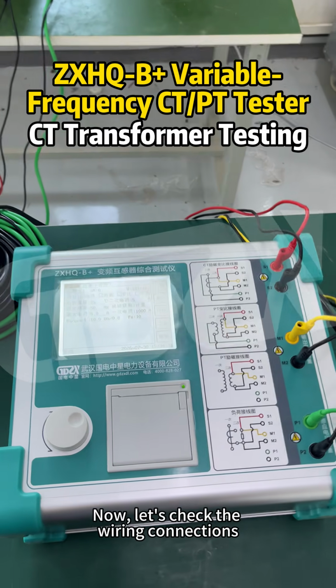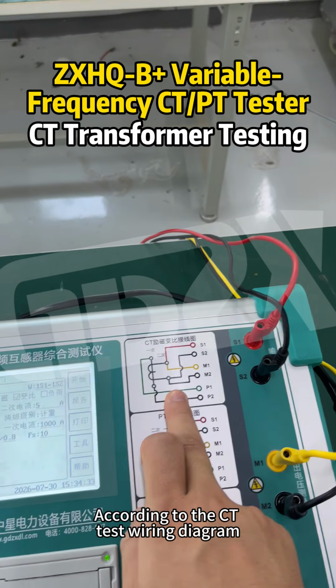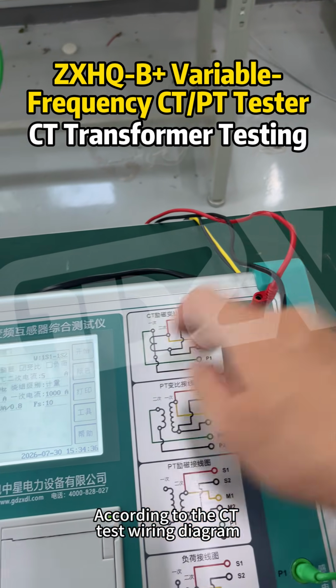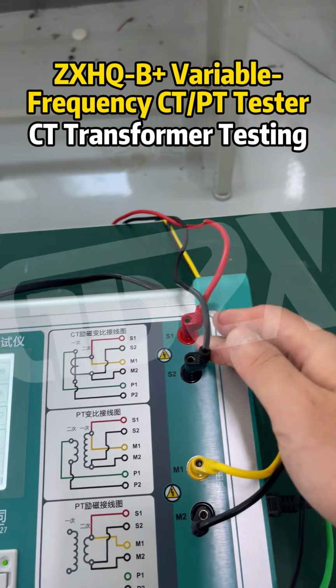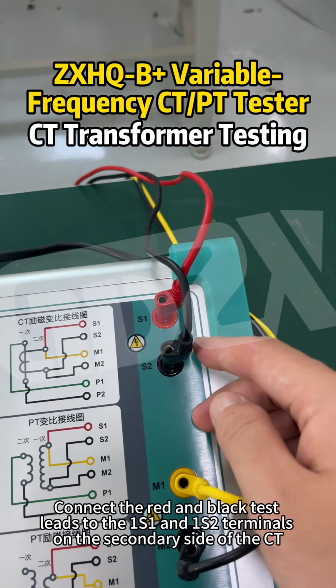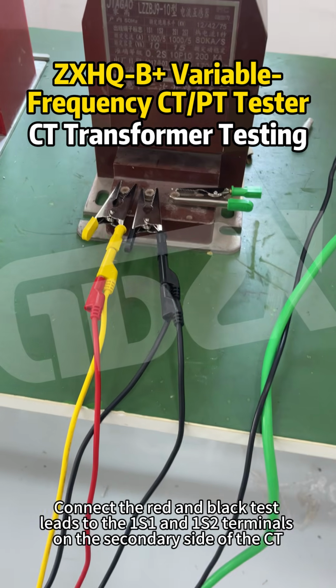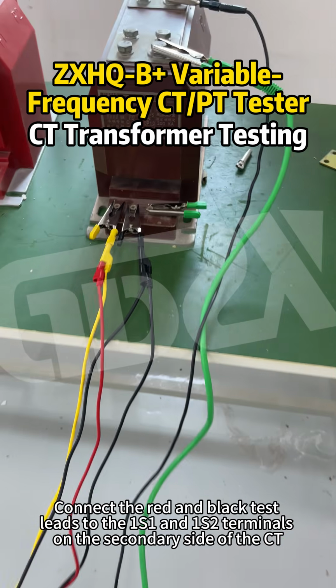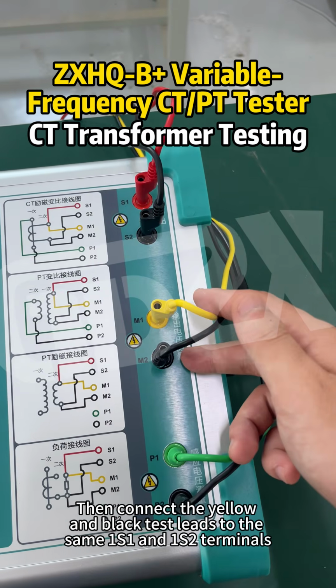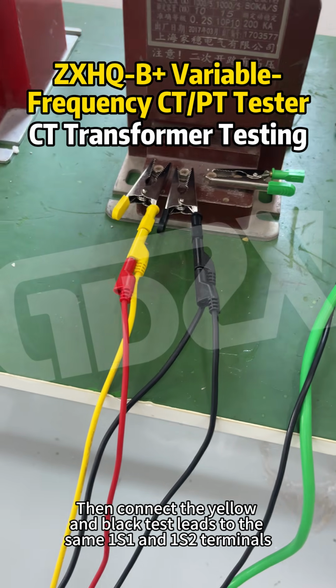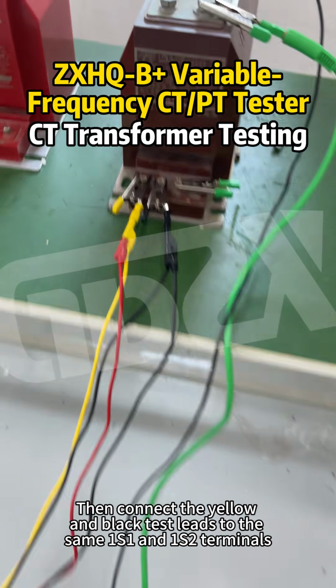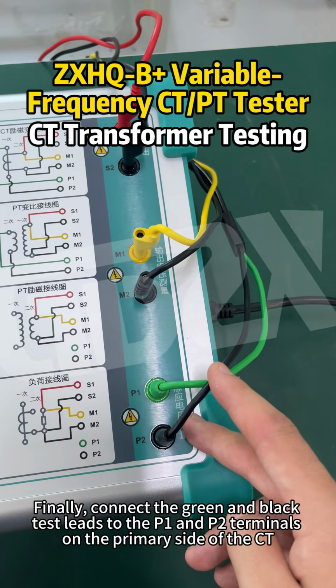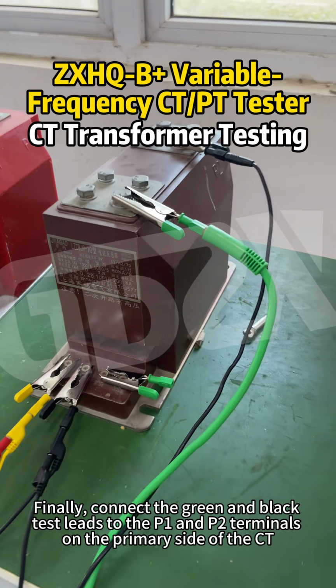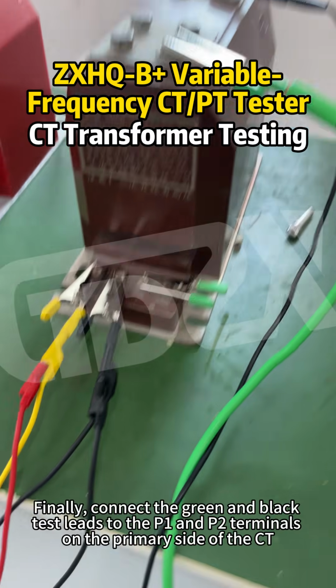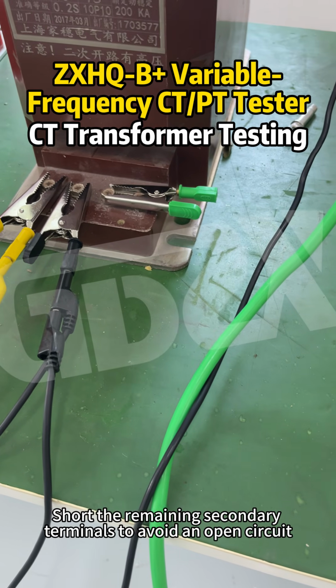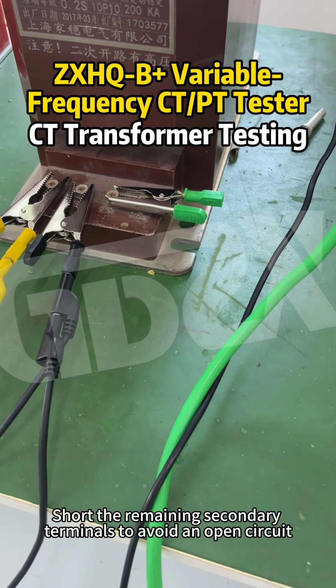Now, let's check the wiring connections. According to the CT test wiring diagram, connect the test leads as follows. Connect the red and black test leads to the 1S1 and 1S2 terminals on the secondary side of the CT. Then connect the yellow and black test leads to the same 1S1 and 1S2 terminals. Finally, connect the green and black test leads to the P1 and P2 terminals on the primary side of the CT. Short the remaining secondary terminals to avoid an open circuit.